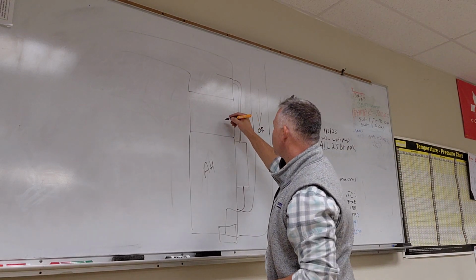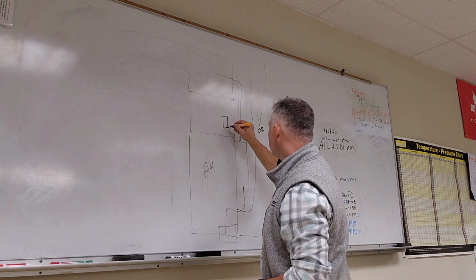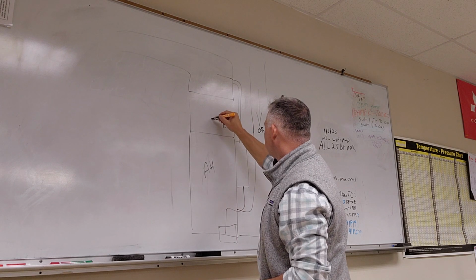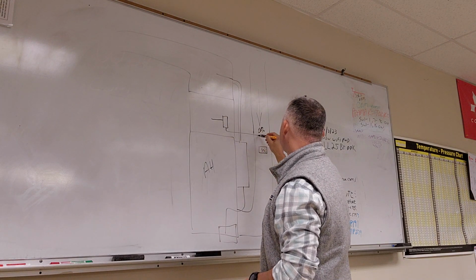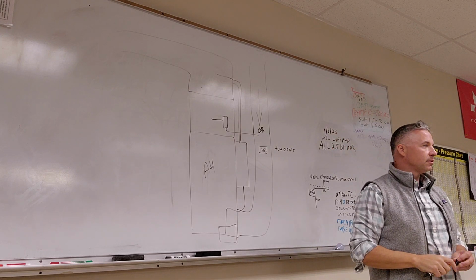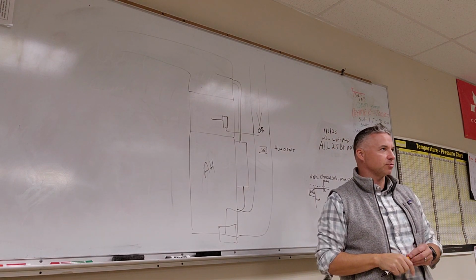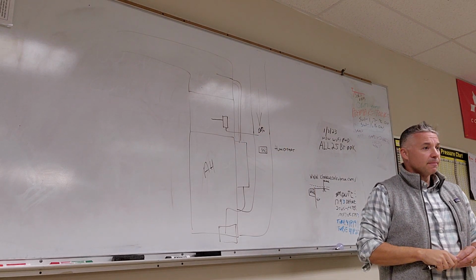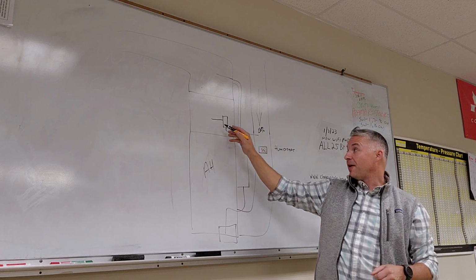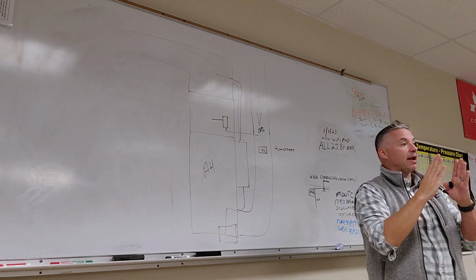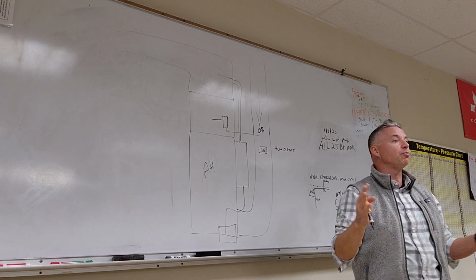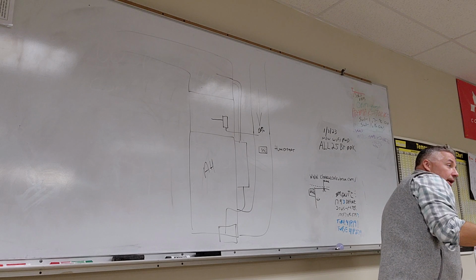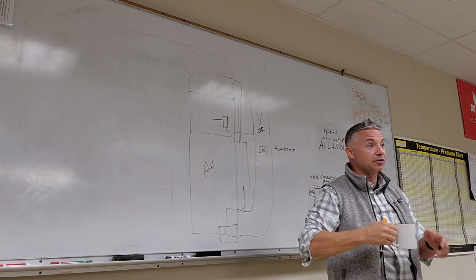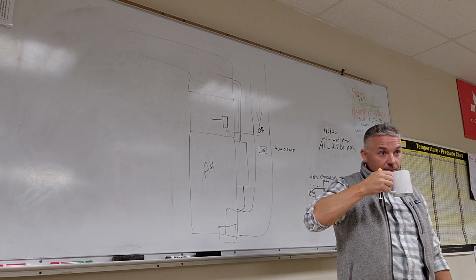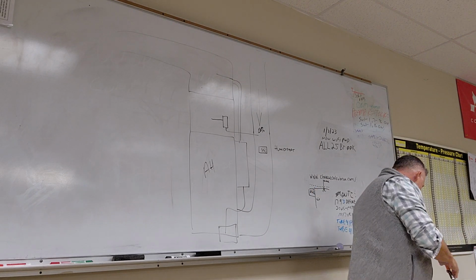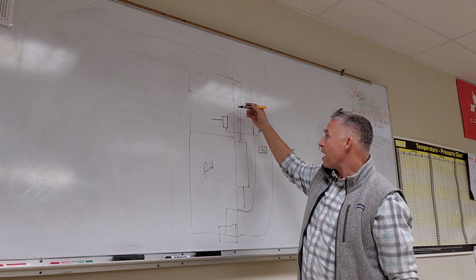So another control that we install is an airflow switch. Okay? And that's going to sense from our supply and sometimes from our return. Sometimes just from one. Okay? And that's a diaphragm pressure switch, a differential pressure switch. Well, it would be a differential if we were sensing from both. But it's a pressure switch. And when the fan comes on and it blows into one side of that, there's a diaphragm inside that switch which closes a set of contacts. We all, at this point, pretty much understand what I mean when I say open contacts and closed contacts. We all pretty much understand that. Okay, we'll dig into that concept a little bit more. So we have fan proving or airflow switch, right?